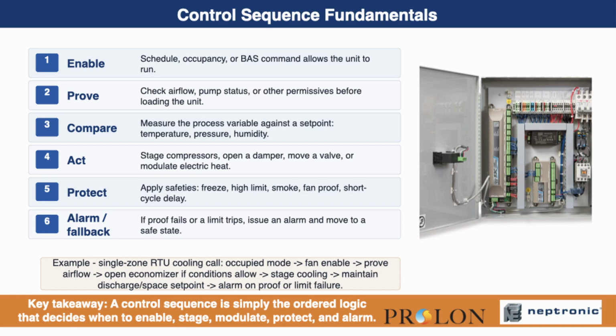Again, using a constant volume packaged cooling-only unit in an office, we can follow the 6 steps on this slide. 1. Enable. The unit is allowed to run because the office is in occupied mode by schedule or command. 2. Prove. The controller starts the supply fan and waits for a fan status proof or current switch to confirm airflow. 3. Compare. The controller compares the office space temperature or discharge temperature to the cooling set point. 4. Act. If cooling is required, the controller enables the first compressor stage, and if the temperature remains above set point, it may bring on a second stage.